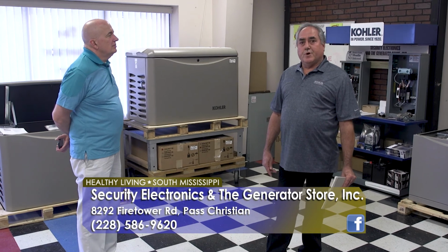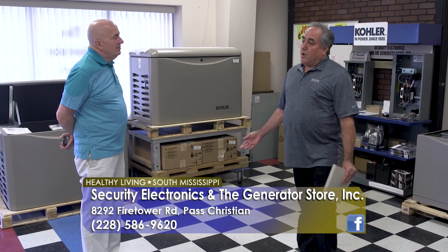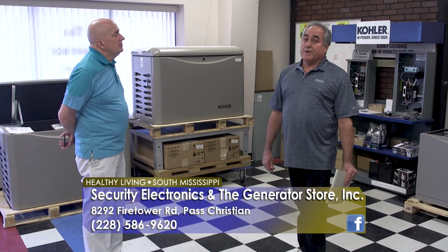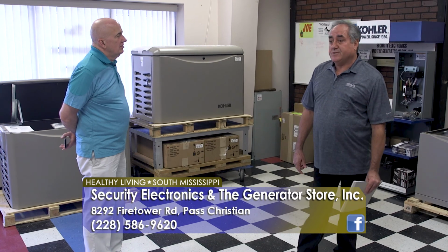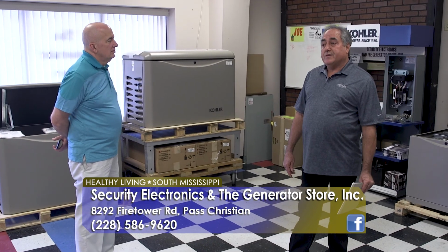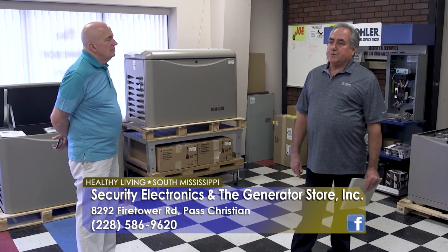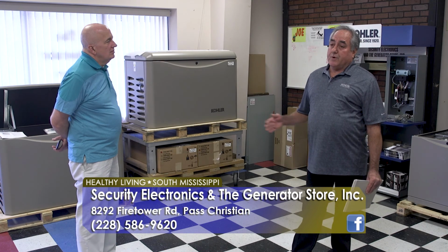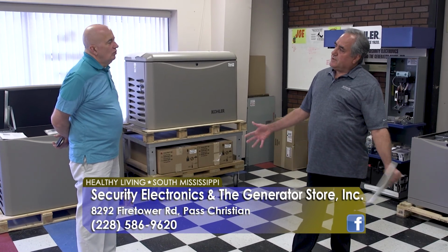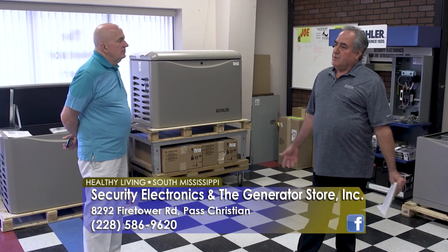I always tell people you don't want to try to have a Thanksgiving Day blowout cookout dinner on your generator. So if your water heaters are on, you need to start your AC units and you're doing some other things, we can load manage or temporarily turn off those water heaters to give the full capacity of the generator to the AC unit or AC units as they start up. And you can prioritize. If AC unit number 1 is the highest priority, and AC unit number 2 is the next highest, you can start those AC units up and then it'll bring the water heaters back on. It's not like we're going to put you in a cold shower, because you've got a tank full of hot water already. Right. So it's a seamless transition that you don't ever miss the fact that the power's been turned off.